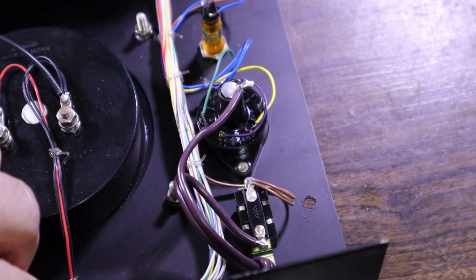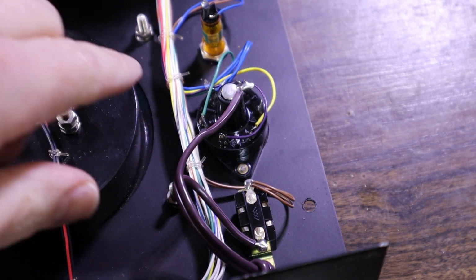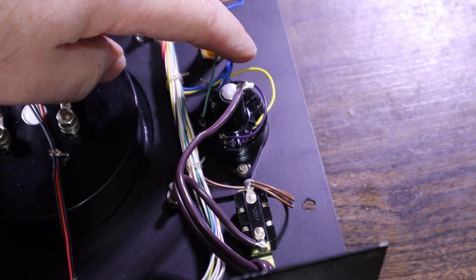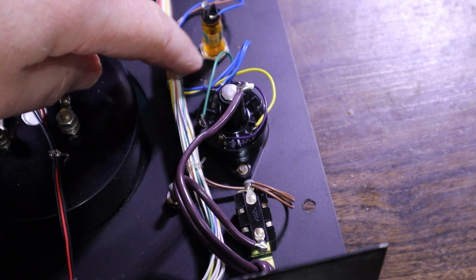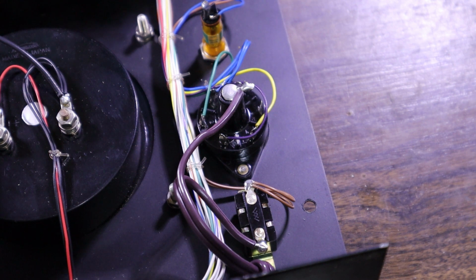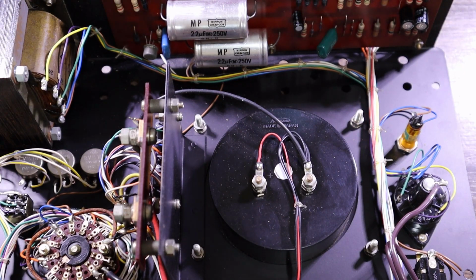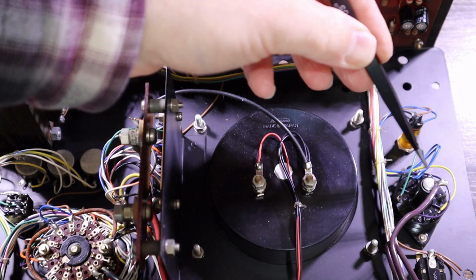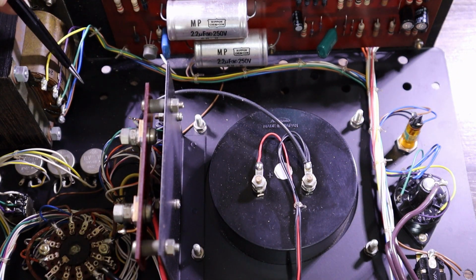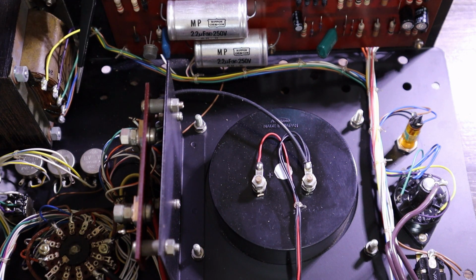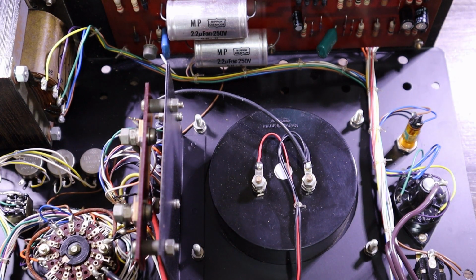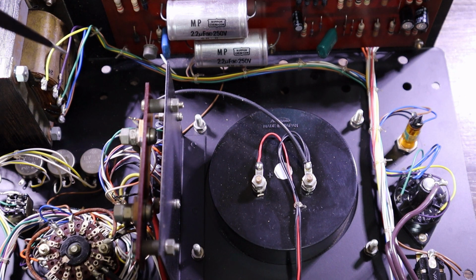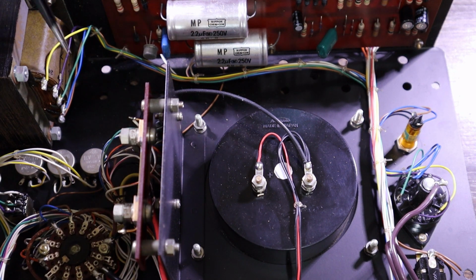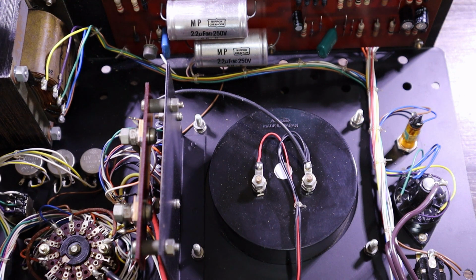So our primary off to the transformer, but our other side of the primary winding is through the fuse into one of the voltage taps. So we will trace that through. We come through from our voltage selector, and our transformer is over here, and we have 100, 117, 240 and sorry, 220 and 240. So yeah, it could be either 220 or 240.